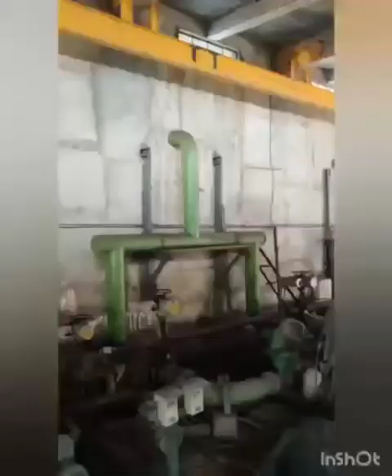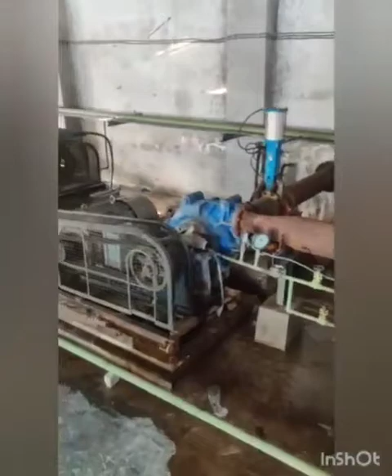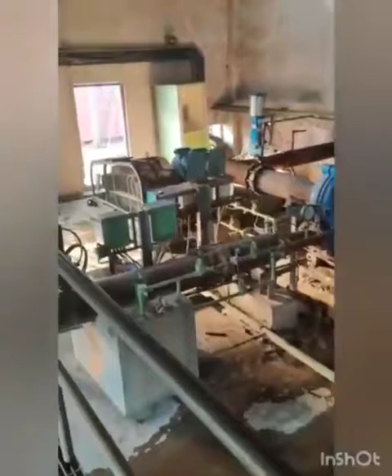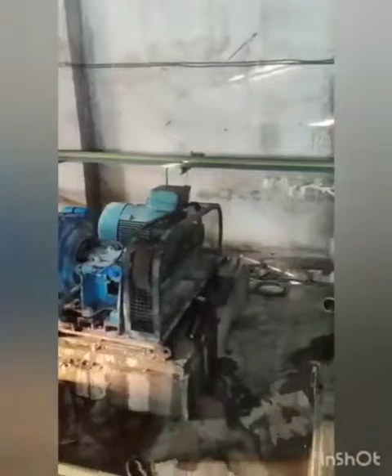For the bottom ash, the water is initially stored in the sump, and then, using series cascading pumps of 600 cubic meter capacity, the ash is mixed with the water and formed into slurry. It is transported to the ash pond, which is located about 3 kilometers from the plant. The slurry is transported through a pipeline of 200 NB dia and then again at 300 NB dia, and is conveyed to the ash pond.